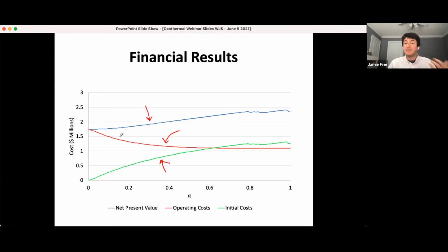As you can see, in this curve for this specific building, given its specific makeup, it actually wasn't an overly favorable installation. Maybe at a small level, it is within the calculation error. They could say, oh, anything up to about 20% might be reasonable if there are other considerations to make. But based on the inputs, there was no very noticeable optimal point from a financial perspective, even though the curve did remain relatively flat in the smaller system size.